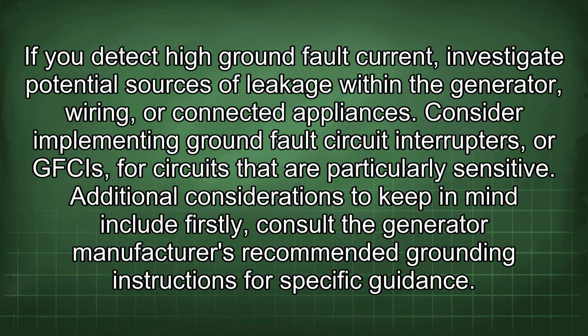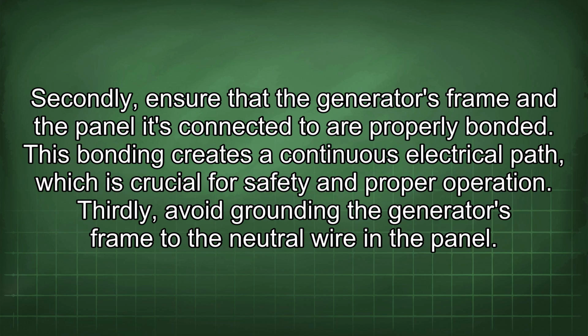If you detect high ground fault current, investigate potential sources of leakage within the generator, wiring, or connected appliances. Consider implementing ground fault circuit interrupters, or GFCIs, for circuits that are particularly sensitive. Additional considerations to keep in mind include: firstly, consult the generator manufacturer's recommended grounding instructions for specific guidance. Secondly, ensure that the generator's frame and the panel it's connected to are properly bonded. This bonding creates a continuous electrical path, which is crucial for safety and proper operation.